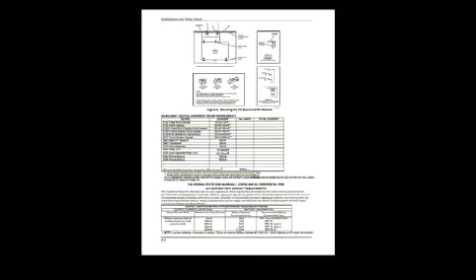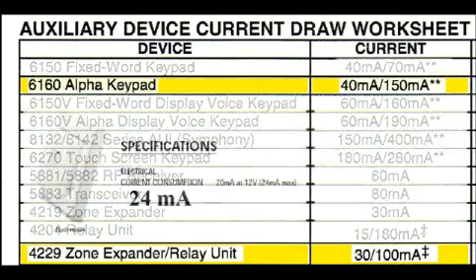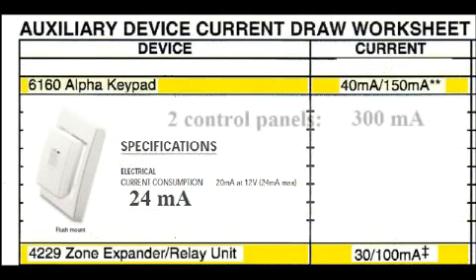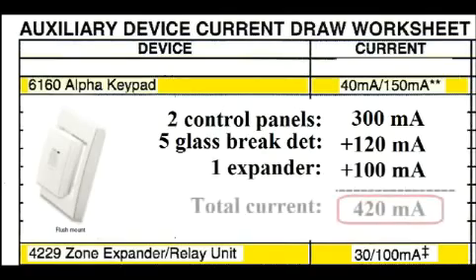The Vista installation manual has a table that lists how much current each of these items will pull. The 6160 keypads pull 150 milliamps each. The expansion module pulls 100 milliamps. The specification sheet for the glass break detectors states 24 milliamps each. Let's add them all up: two keypads at 300 milliamps, five glass break detectors at 120 milliamps, one expansion module at 100 milliamps. Total: 420 milliamps being used.